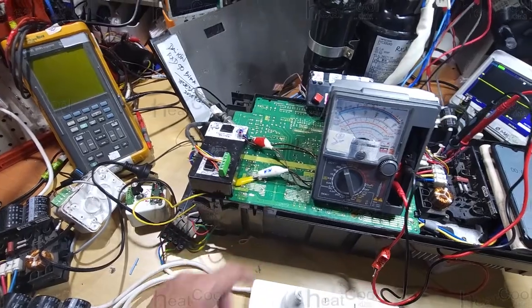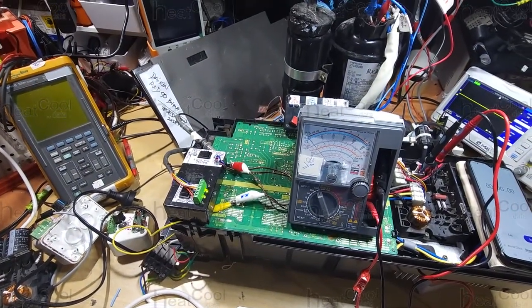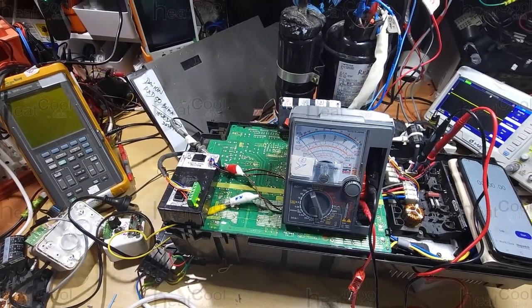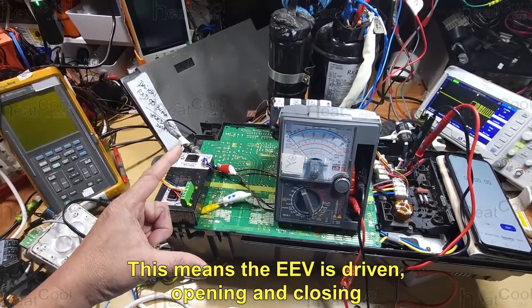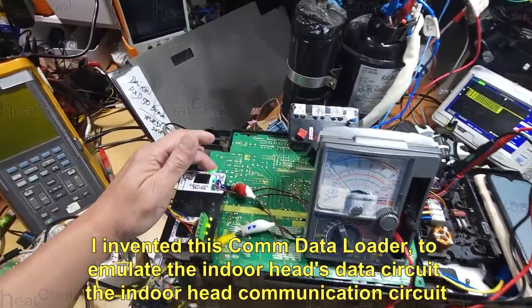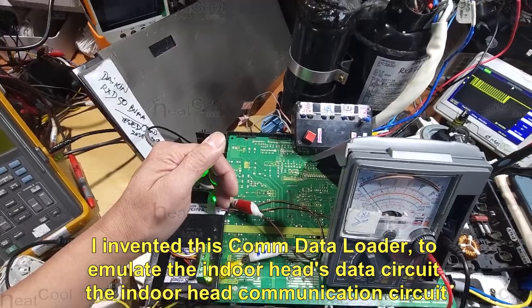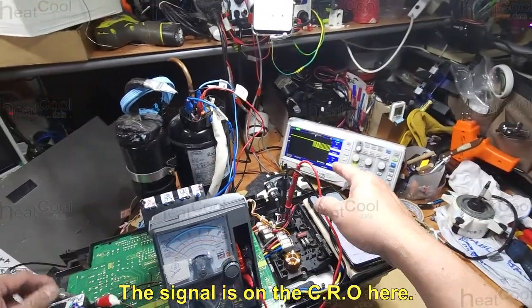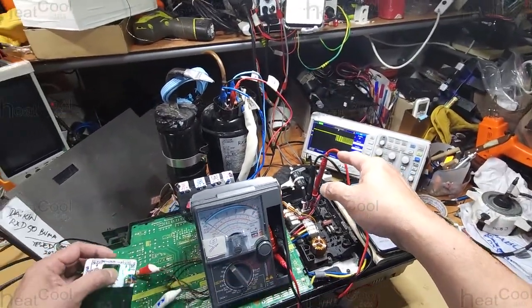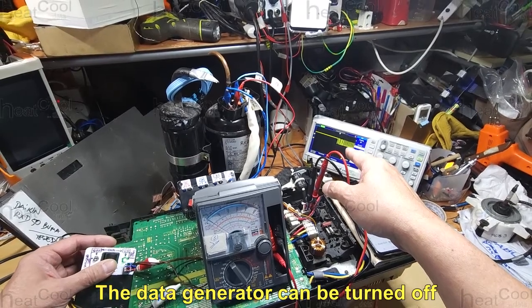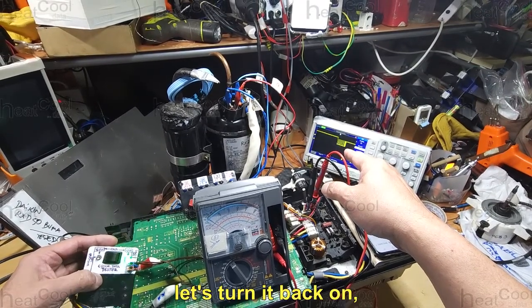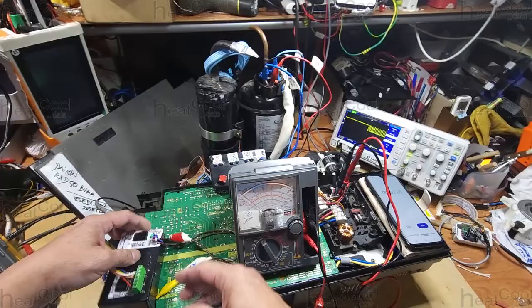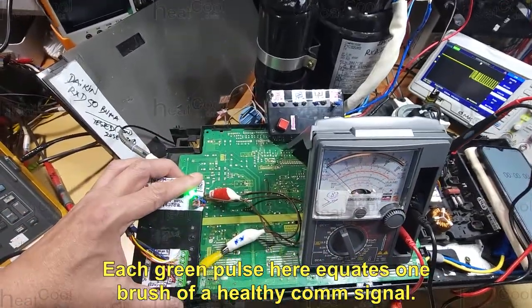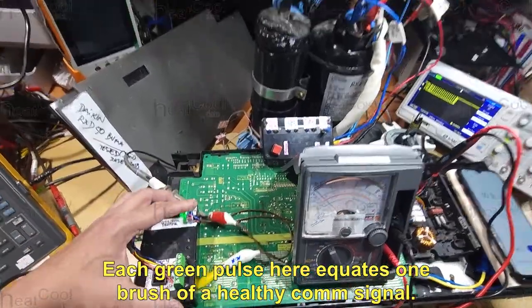These lights indicate the EEV's Darlington drivers are working. This means the EEV is driven opening and closing. I designed this COM data loader to emulate the indoor head's data circuit. The signal is on the DSO here. The data generator can be turned off. Let's turn it back on. Each green pulse here equates to one burst of healthy COM signal.